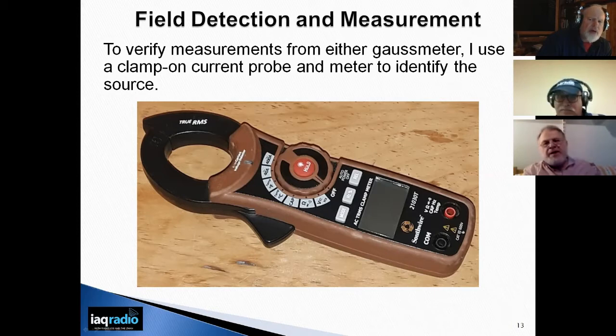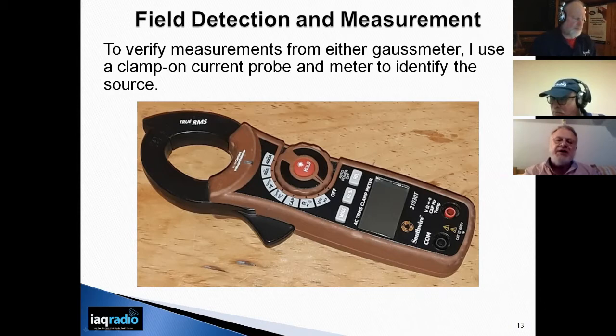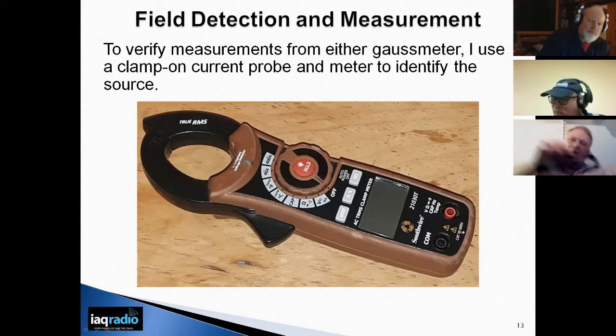As I said, with that one client where they had a problem with the HVAC unit, they noticed a correlation - the field emerged all over the house whenever the HVAC unit was on. I'm thinking, okay, I can walk by the HVAC unit and see a field there, but am I absolutely sure that's the case? So using this meter, I can clamp onto the feed of the HVAC, and by measuring the current I can determine whether that's actually the source of the magnetic field.